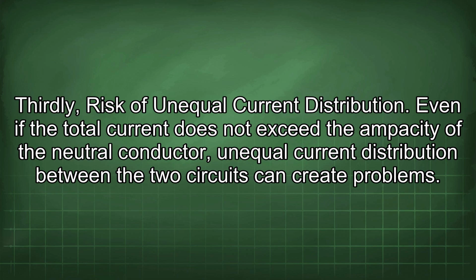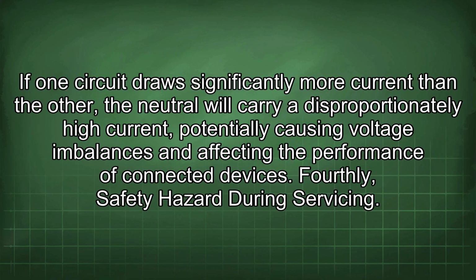Thirdly, risk of unequal current distribution. Even if the total current does not exceed the ampacity of the neutral conductor, unequal current distribution between the two circuits can create problems. If one circuit draws significantly more current than the other, the neutral will carry a disproportionately high current, potentially causing voltage imbalances and affecting the performance of connected devices. Fourthly, safety hazard during servicing.